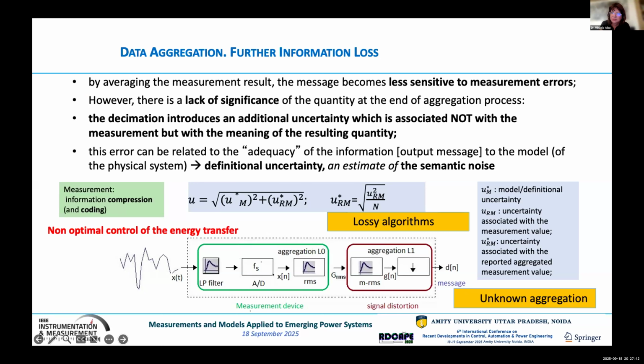Then we use the modern way of digital systems and measurements, and what we obtain at the output of the analog to digital converter, we don't transfer anymore, although we try with these new standards of sample values recently, but it's very, very low, acquiring the realm of power system engineers. And then we decimate. And this decimation, at a first glance, is presented as a triumph, because by decimation you reduce the associated uncertainty with each measured sample.